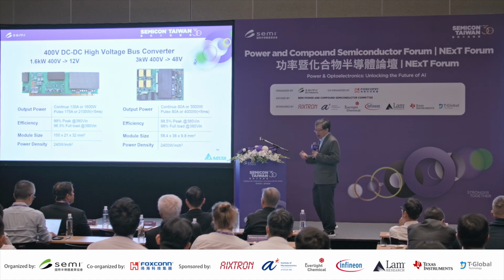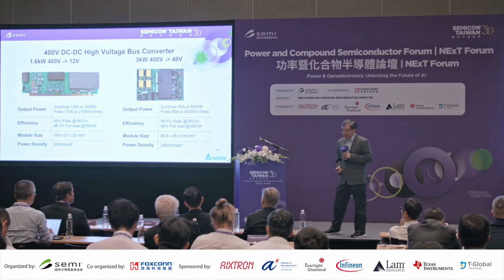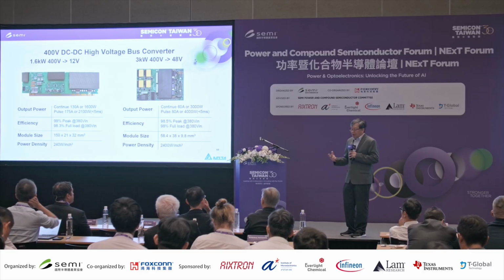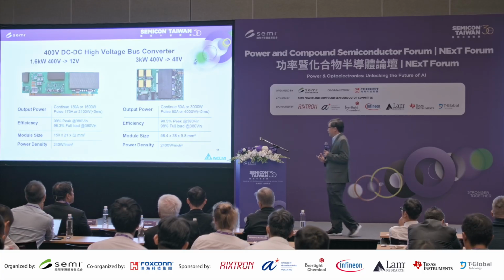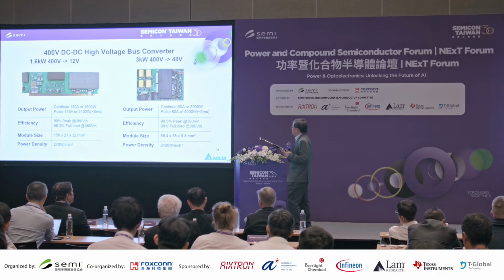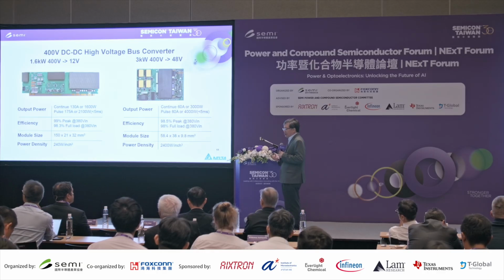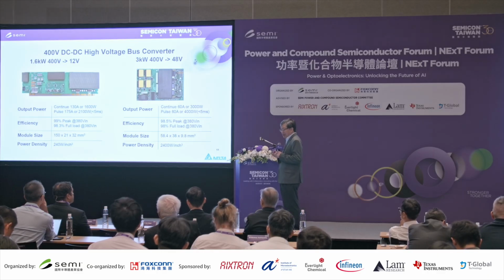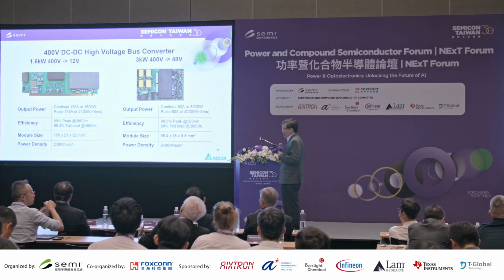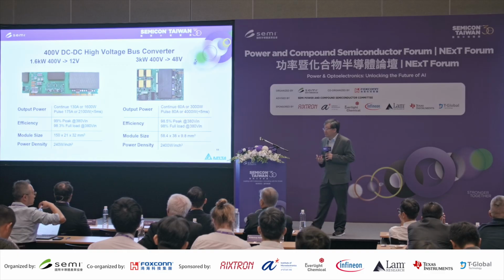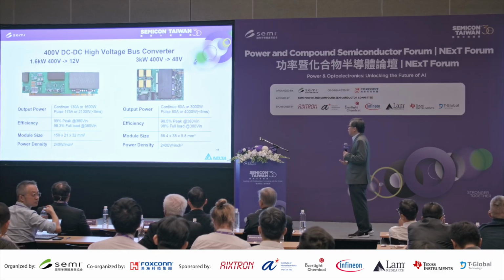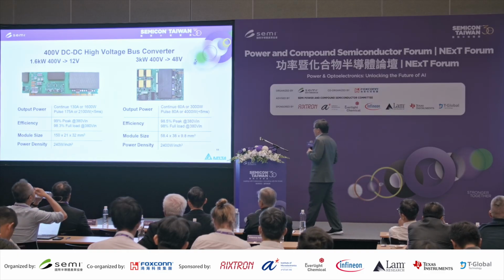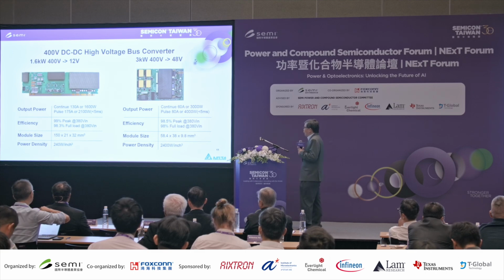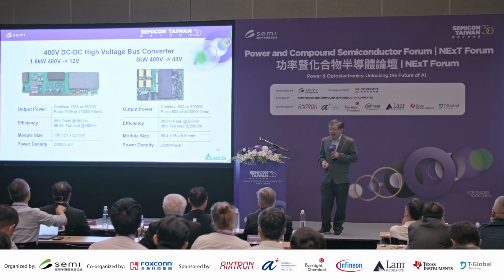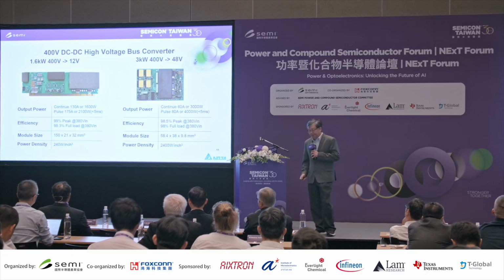We already established this for servers. If one unit needs 10 kilowatts, we just put 3 or 4 modules in parallel, so you occupy a very small amount of space. Compared to AC to DC, if you want to handle 10 kilowatts, your power module would become significantly larger—there's no way you could put it into the server. So modularization along with high voltage DC is a future trend, and it's actually coming around the corner.